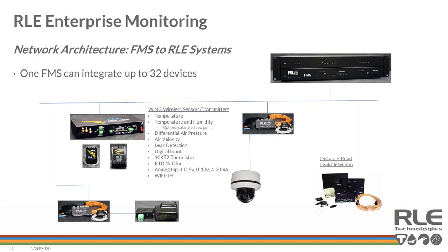The distance-read leak detection system identifies the distance at which a leak was detected. What you do with that information is ultimately a mitigation path and planning we hope to enable. A lot of times it's a scramble on the back end — what do we do now? If you spend a little time on the front end for risk mitigation planning, you can execute a sequence of cause-and-effect actions: if water leaks, do you just alarm, send a signal to close a water valve, or trip a relay to activate a security system?